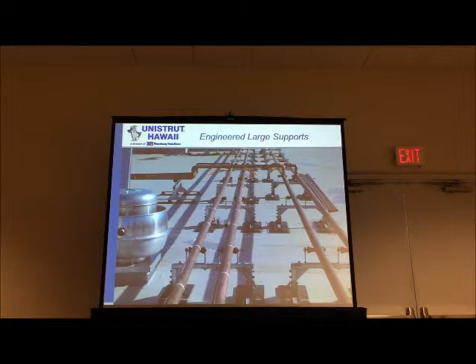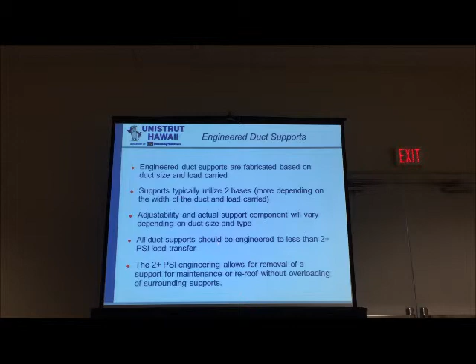Here are more pictures of other supports, and you have a variety of bases and configurations in order to meet the kind of supports required for your system. Duct supports, we're going to keep hammering this because that's the message I want you to get: as you leave the room, 2 pounds a square inch. Load transfer should be all there is when you are considering your non-penetrating equipment supports.